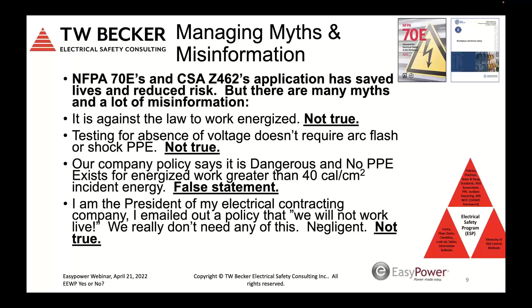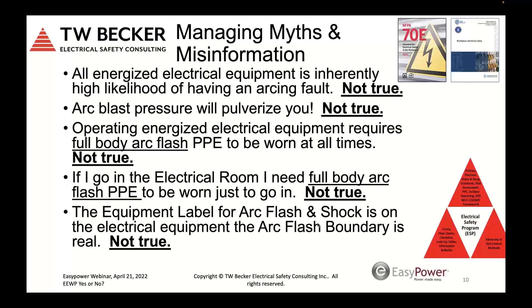That's not true either. Operating energized electrical equipment requires full body arc flash PPE at all times. That's not true. If I go into the electrical room, I need full body arc flash PPE just to go into the room. That's not true either. And the arc flash and shock equipment label with the results from the arc flash hazard incident analysis study, it's on the electrical equipment. The arc flash boundary is real right now. That's not true, right? The work task determines if the worker is exposed to shock and an abnormal arcing fault and an arc flash, depending on the voltage of the electrical equipment to sustain the abnormal arcing fault. Just again, embellishing on some of these myths and misinformation, and some of these directly relate to the energized electrical work permit. So on the screen, I've got sort of 5 editions of 70E and Z462.